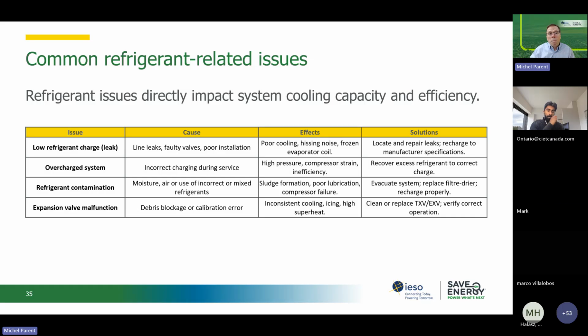When you're overcharged, you may sometimes see freeze-ups, but most of the time what you'll see is really high head pressure, because all of that extra refrigerant goes onto the condenser side, which reduces the effective area that you have on your condenser. It will reduce what's called your subcooling. So if your operating team knows how to check for the compressor high pressure and how to check for subcooling, and they see very low subcooling and very high head pressure, they know that they are overcharged. And now you can actually call the refrigerant tech and tell them, we're almost certain that we have an overcharged system.